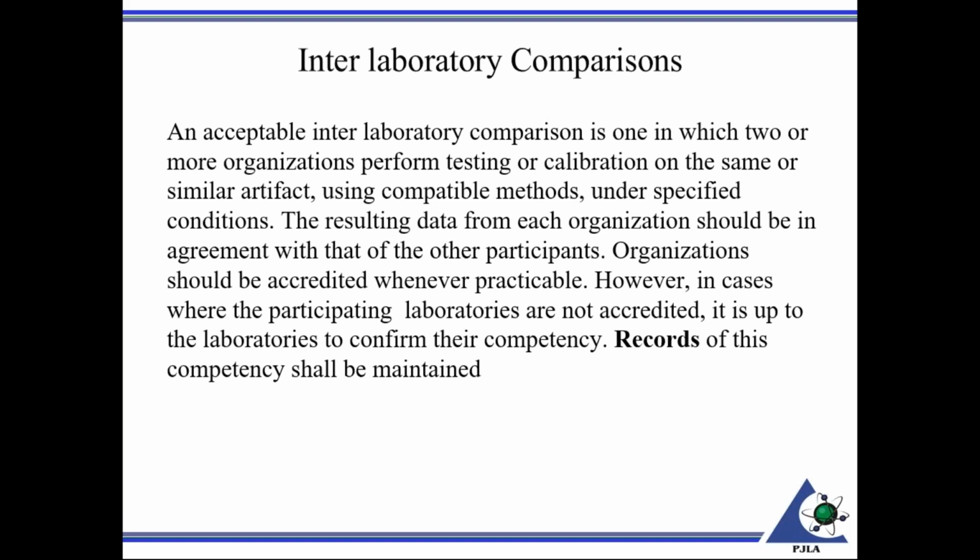So prior to our latest revision, we used to specify that the other organizations had to be accredited. And if they weren't accredited, they basically had to jump through the requirements for traceability. That's our policy in PL-2 for traceability, where we go through an LF-123, because you could be accredited or not accredited, and provide traceable results. So we found that with testing labs, that sometimes was not always the key factor. Hence, we changed that requirement from being accredited to being competent.